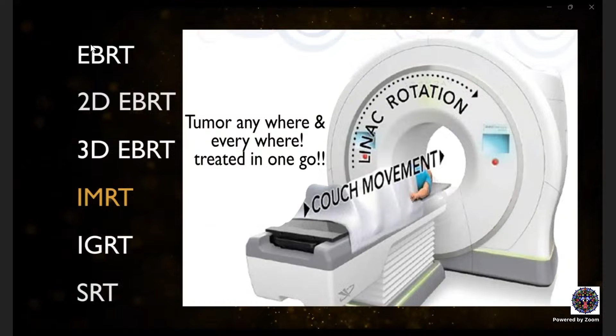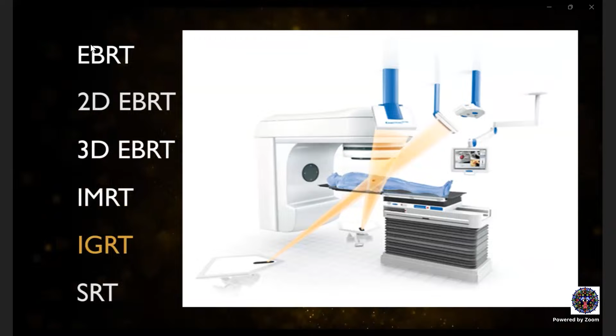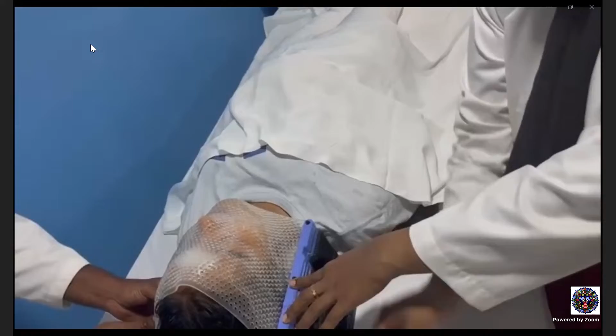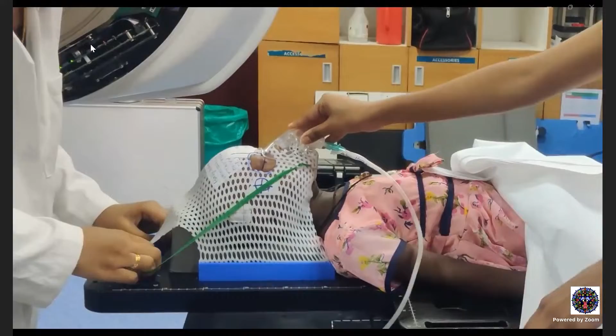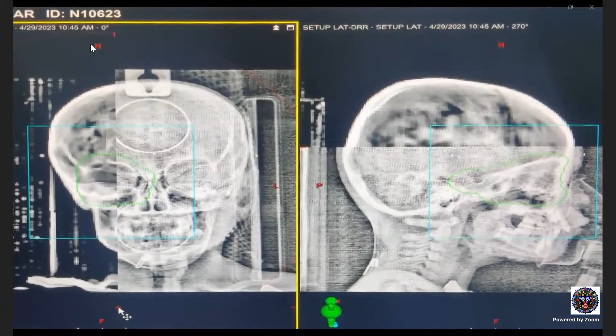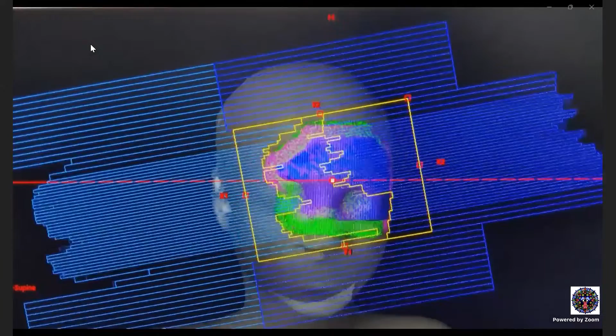In rapid arc modification of IMRT, with opening and closing of multi-leaf collimators, dose painting is achieved. Tomotherapy works on a principle of IMRT and delivers radiation by rotating around the body, aiming targeted beams at tumors from many angles. IGRT, that is image-guided radiotherapy, the workflow for which includes preparing a face mask. Positioning with mask and infrared positioning. Verification with X-ray, CT scan or MRI for anatomical matching of tumor. Correction with 6 degrees robotic couch, snap verification at every couch angle, and finally the treatment delivery.